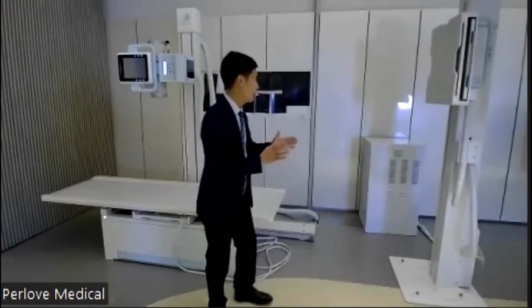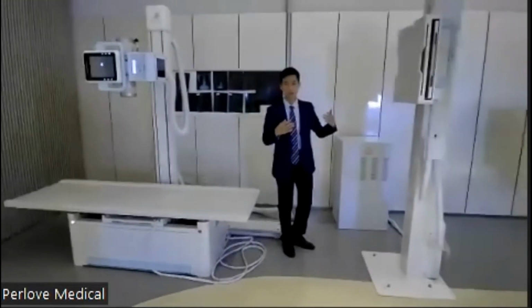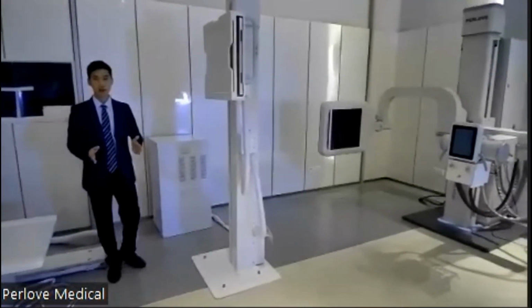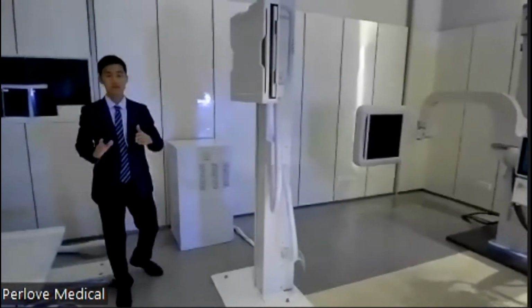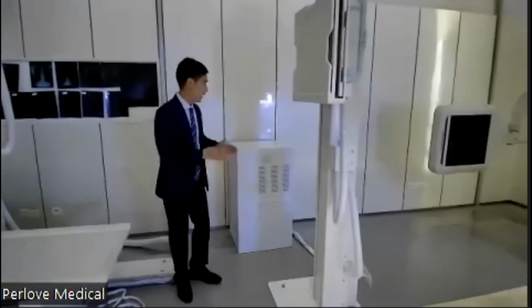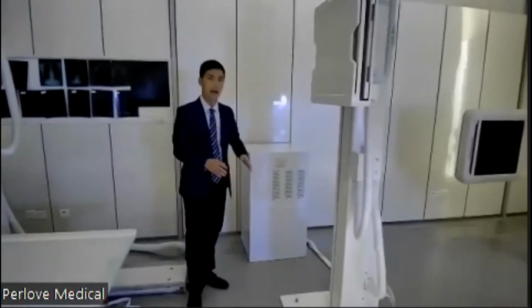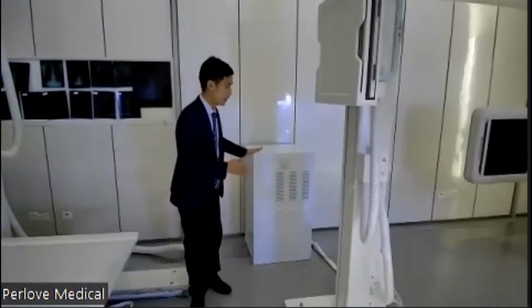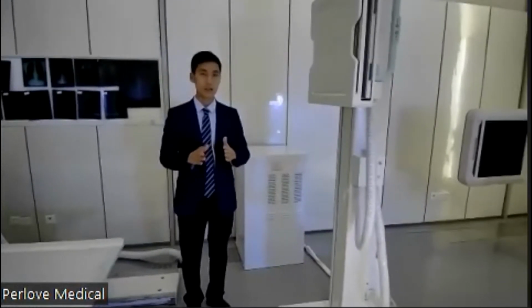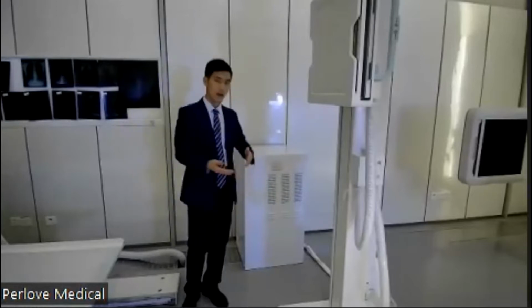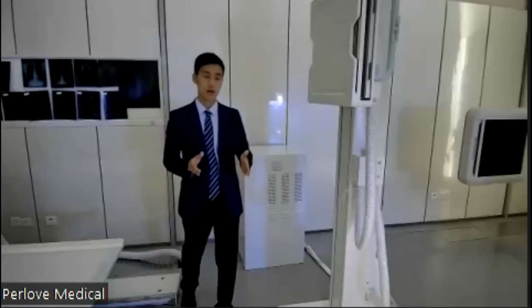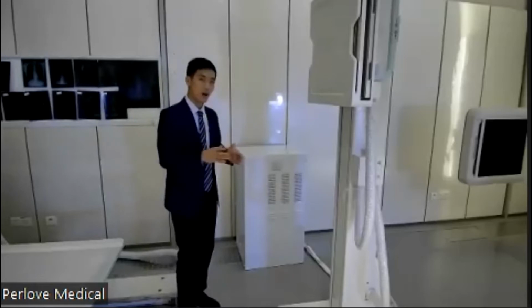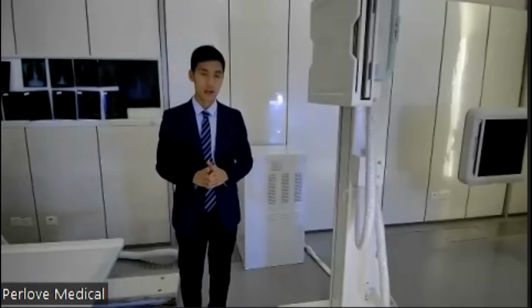And let me begin with some basic parameters of this machine. I'm very proud to declare that this machine has some of the best parameters in the market. Firstly, the generator. The high-end generator is developed by Perlove Medical ourselves. 65 kilowatt output power, 800 milliampere tube current, which is enough to support all kinds of clinical applications. And I want to especially mention that this generator has 500 kilohertz inverter frequency. This is a very exceptional parameter you will never see in the market. Most generators in the market are 50 kilohertz, 200 kilohertz, but our generator is 500 kilohertz, the highest in the market, which means our machine has the best hardware foundation for excellent X-ray quality.